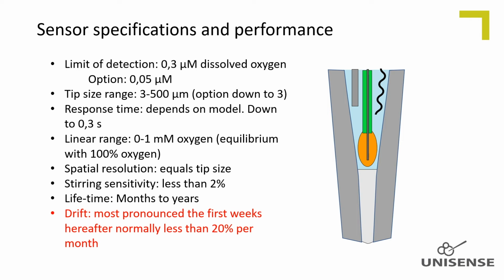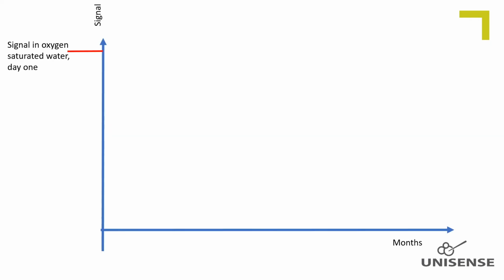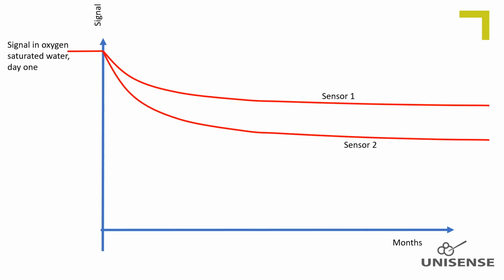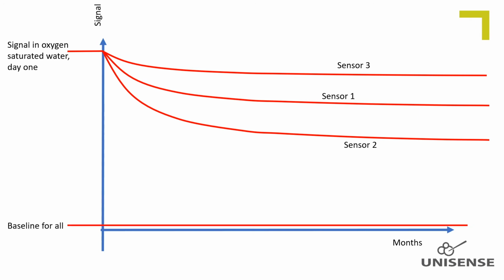some time is minimal. As the sensors are handmade, the drift varies among the oxygen sensors, exemplified here with 3 oxygen sensors starting with the same sensitivity, but after some time the signals are different. Thus, it cannot be predicted precisely how much drift a user will experience. We recommend calibrating whenever possible and convenient for all important measurements. The baseline does not change significantly with time.